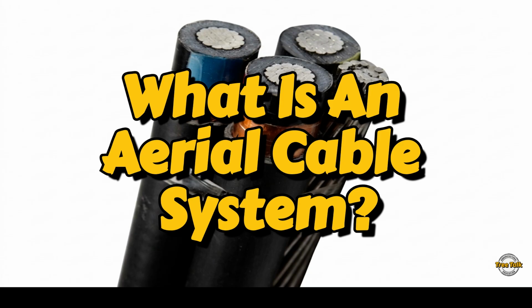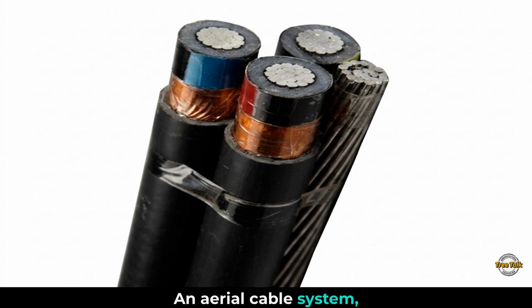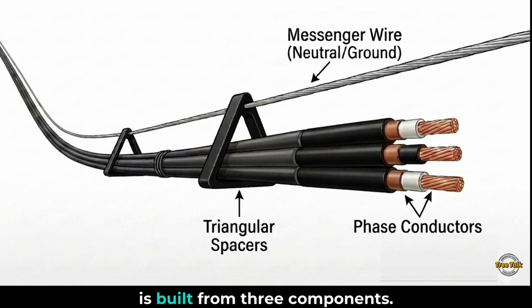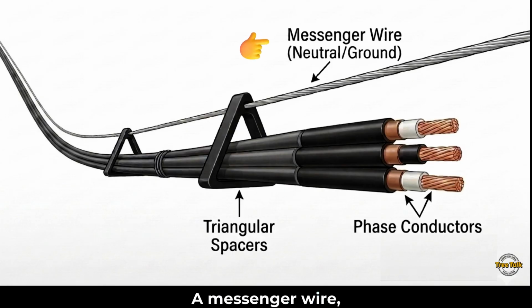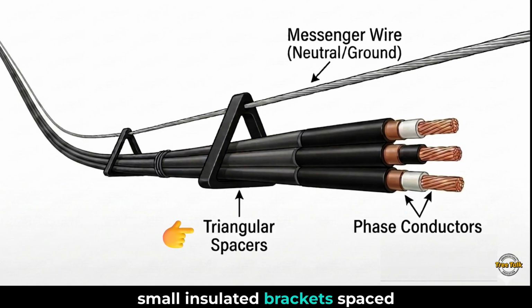What is an aerial cable system? An aerial cable system, commonly called Hendrix cable after one of the major manufacturers, is built from three components: covered conductors, the actual power-carrying wires, wrapped in layers of insulating polymer material; a messenger wire, a separate, bare grounding cable that carries the physical weight of the whole system and keeps it strung between poles; and spacers, small insulated brackets spaced along the span that hold the three covered conductors in a fixed, compact triangle position relative to the messenger.